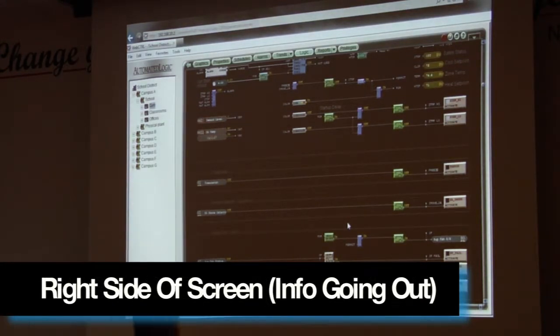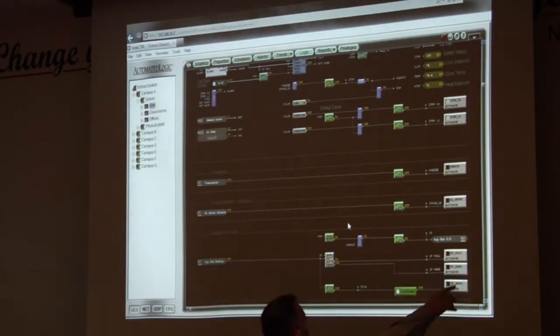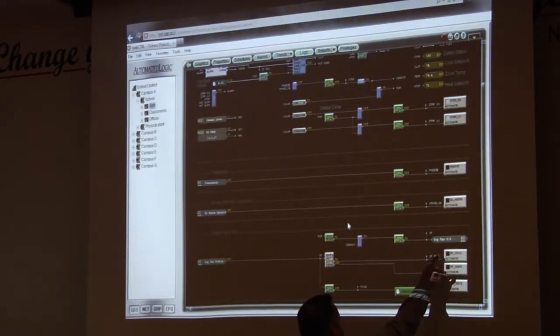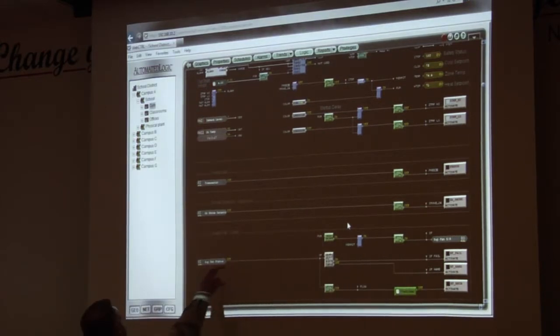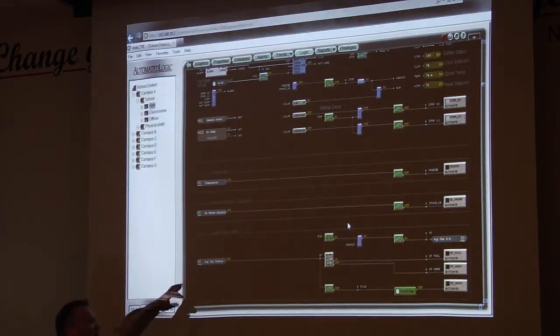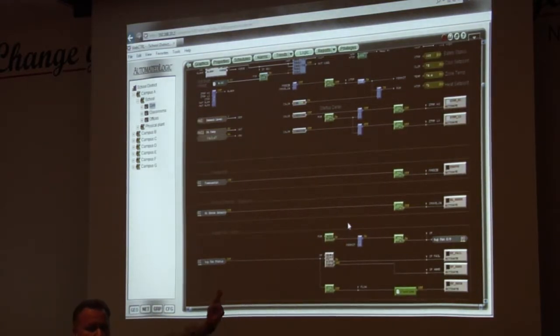If you scroll down, or depending where you're at, it could be chiller start stop. If you notice, I have supply fan start stop here. So that's going out to a relay, okay? Which actually, if I look on my panel, I can see it's turned on now. And then, of course, the status coming from it is here on the left. That's information coming in. So I'm wired to a current sensor. And when I tell the command to turn on and the fan starts, the current sensor senses voltage in the line, and then I get status saying here, yes, the fan has started, all right?